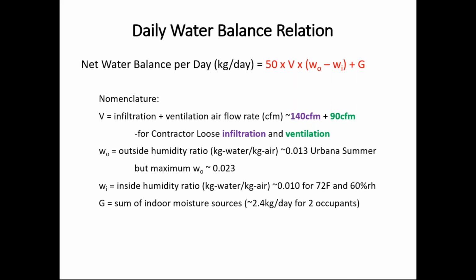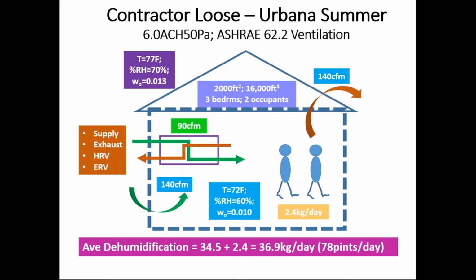Those are the things we need in order to calculate the water. And if we look at these three homes for contractor, loose, tight, and smart, hopefully this slide's not too busy, but for our 2,000 square foot home, two occupants, with the amount of infiltration and ventilation in Urbana in the summer, the average dehumidification would be about 37 kilograms or liters per day, or roughly about 80 pints per day.